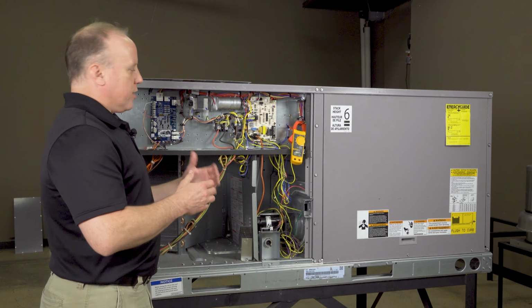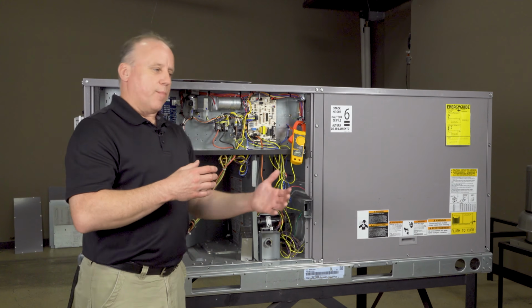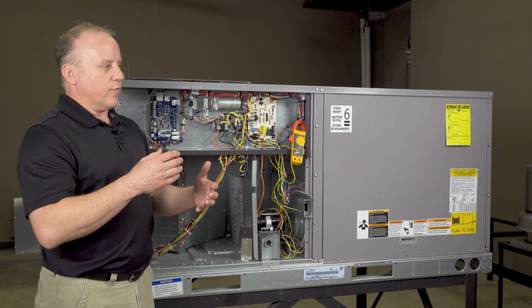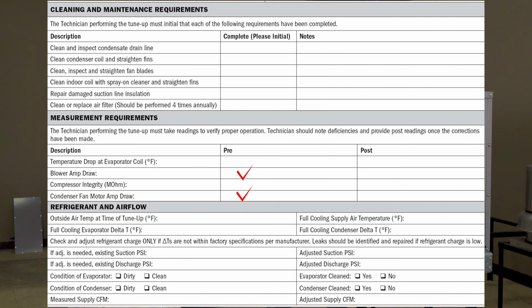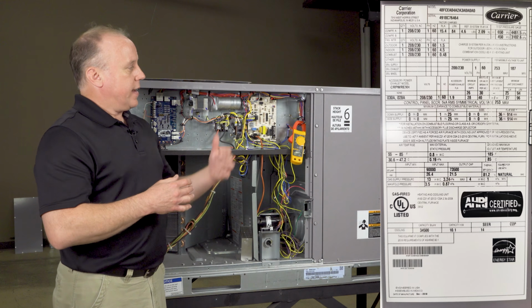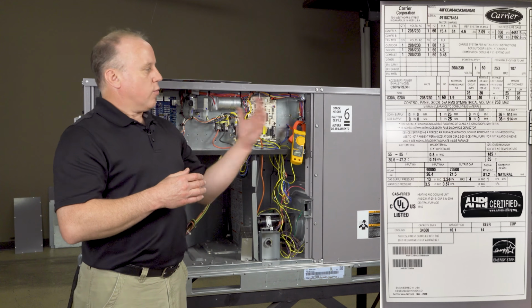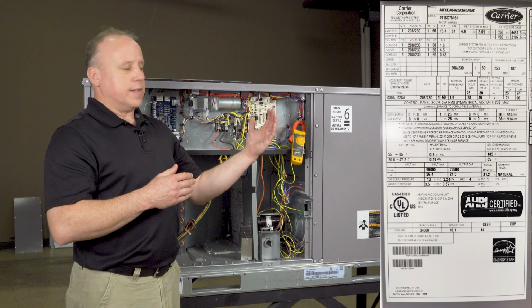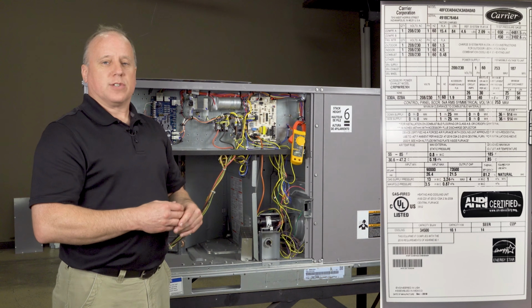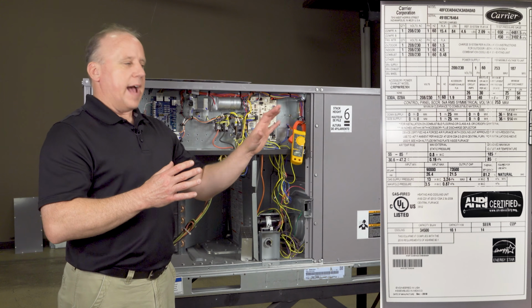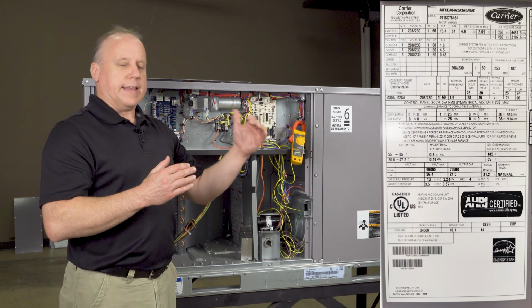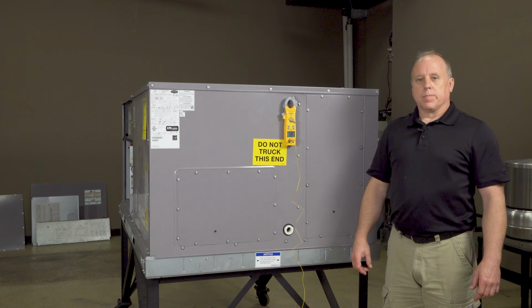On the compressor, if we have high amp draw, is there a problem with the compressor? Is the refrigerant charge off? Is there something else going on there? Amp draw is going to give us an indicator of what may be going on in the unit. So it's a good reference when you're just doing a check on a unit. As you're doing maintenance, get the amp draws, reference your information tag, and make sure those amp draws are approximately at the label or ideally maybe just below.